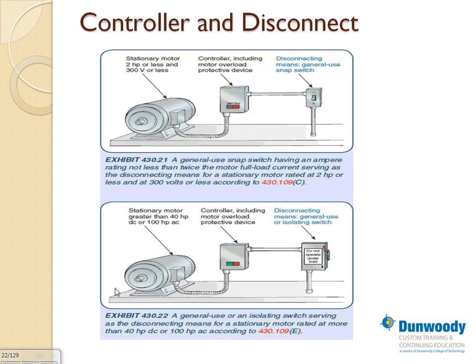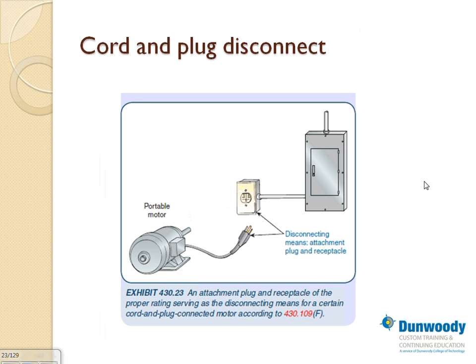So that's just a few things about the controller, the disconnect, the controller. General use snap switch or NEMA, heavy duty or non-heavy duty on the wall. Plug in. Portable equipment, you can plug them in. A lot of machines, if it's especially portable equipment, plug in, that will act as your disconnect. A lot of equipment and appliances, the plug is rated as a disconnect.